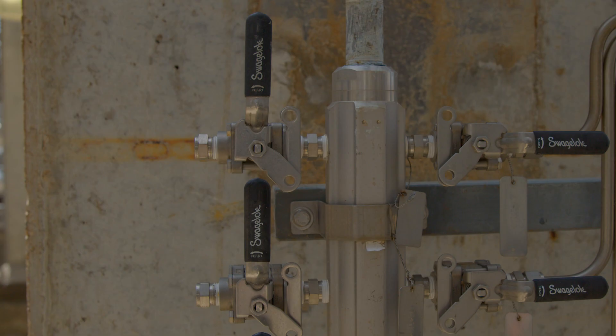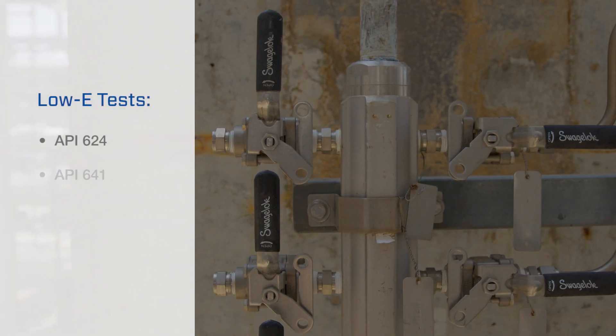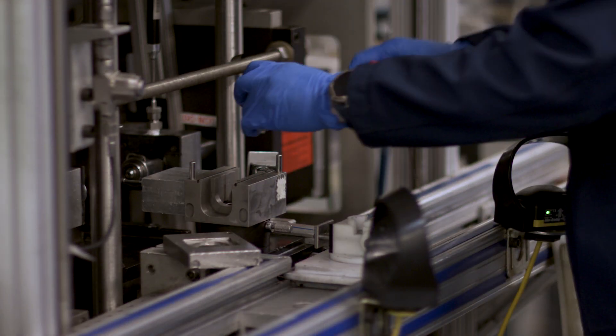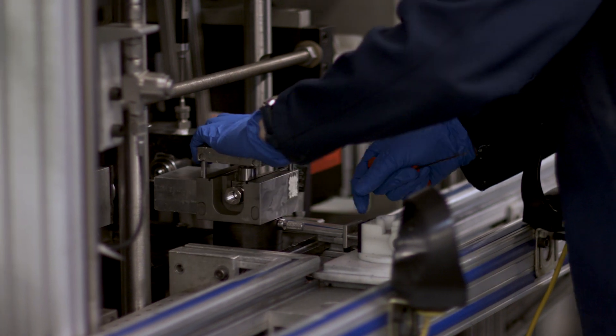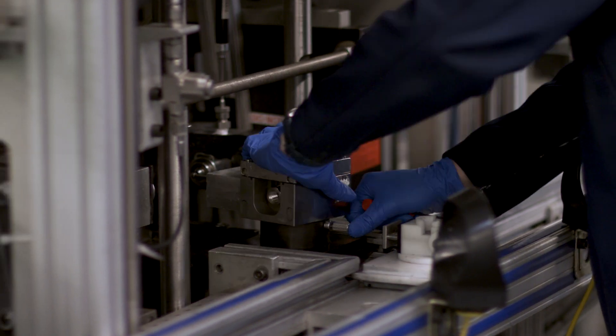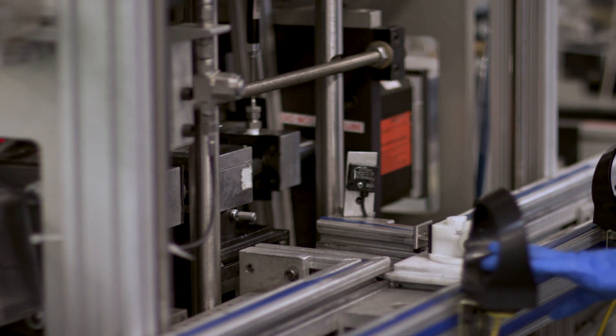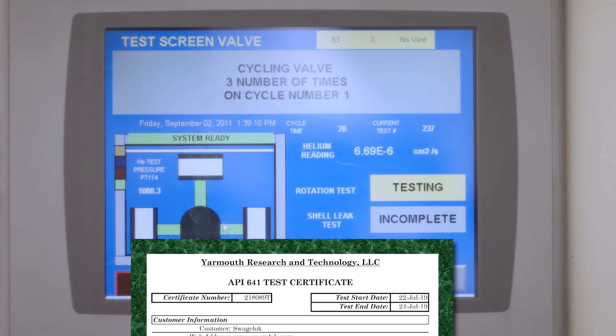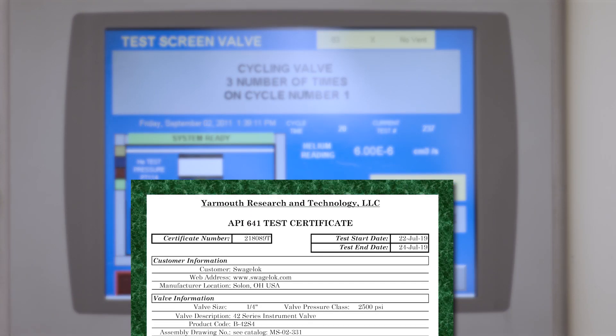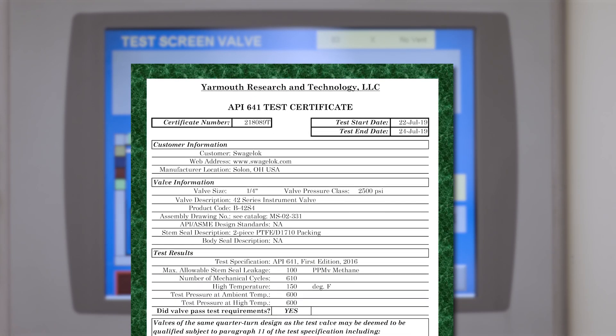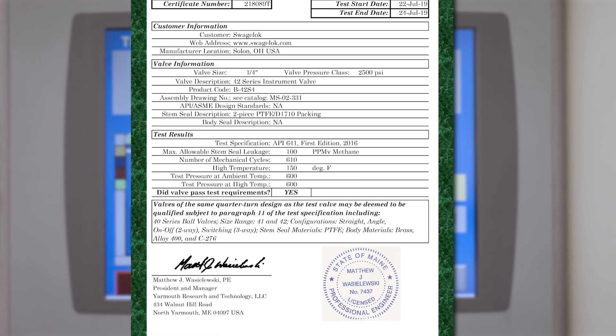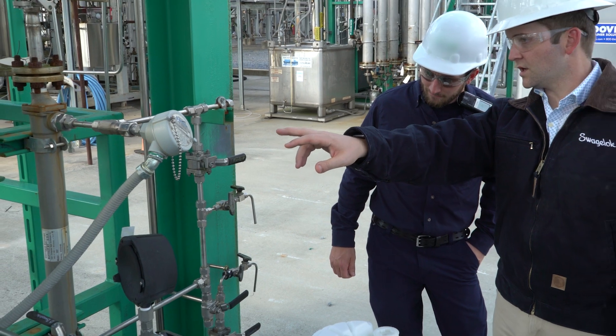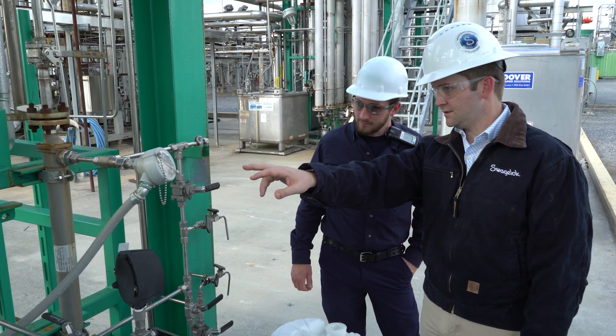Fortunately, there are industry standard tests that can help determine if a valve is truly a low-e valve. Ideally, these tests should be conducted at a third-party laboratory and not by the valve manufacturer. Certification should then be available from the manufacturer as documentation, including a seal from the third-party lab, the testing location, and the results. Selecting valves that come with one of these certifications is the best way to prevent fugitive emissions.